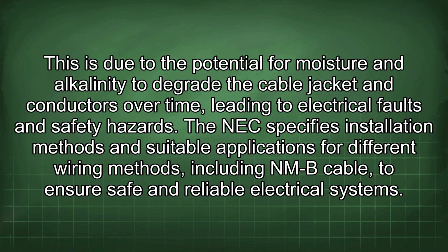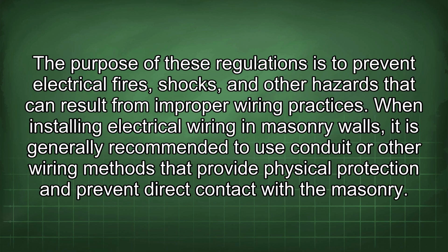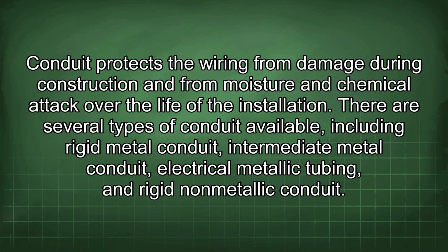The NEC specifies installation methods and suitable applications for different wiring methods, including NM-B cable, to ensure safe and reliable electrical systems. The purpose of these regulations is to prevent electrical fires, shocks, and other hazards that can result from improper wiring practices. When installing electrical wiring in masonry walls, it is generally recommended to use conduit or other wiring methods that provide physical protection and prevent direct contact with the masonry. Conduit protects the wiring from damage during construction and from moisture and chemical attack over the life of the installation.